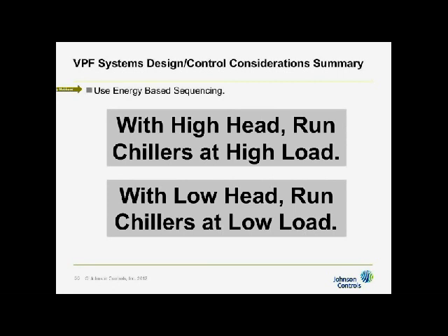Another consideration with VPF systems and design and control is energy-based sequencing. Energy-based sequencing is when you look at what we have typically always used, load-based, and you mix it with energy-based, depending upon conditions that are going on with the weather.